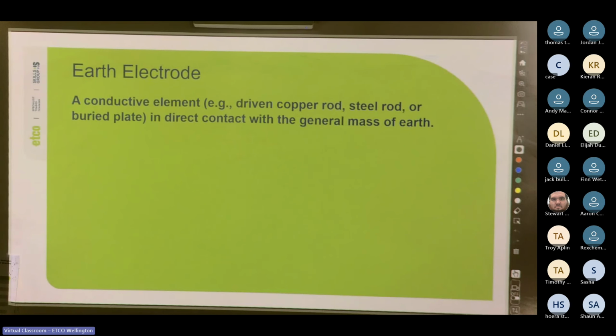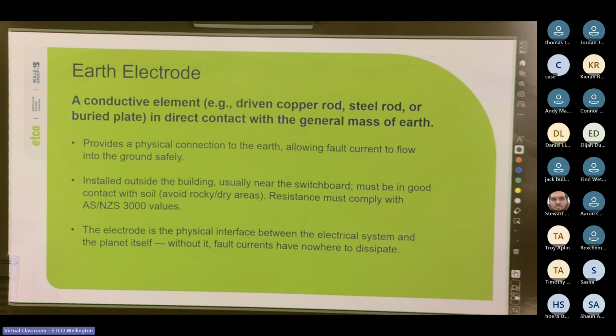Cool. So the earth electrode, it's our anchor to the earth. In New Zealand's MEN system, it doesn't carry huge currents under normal conditions, but in a fault, it ensures the system remains bonded to the true earth potential. So it provides a physical connection to the earth, or what we call the general mass of the earth. It's installed outside the building, as close to the switchboard as we can. And the reason it needs to be outside is because it needs to be accessible for inspection. So if we put it under the house or under a concrete slab, it's not accessible for inspection. Yeah, it's a physical interface between our electrical system and the planet.